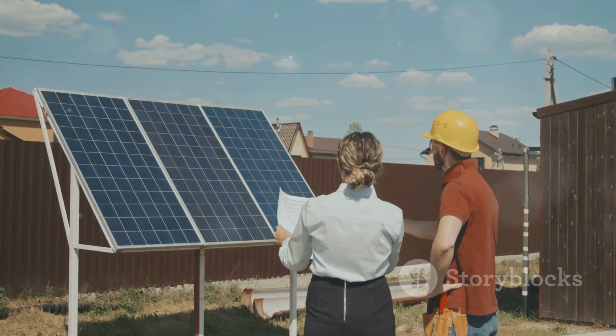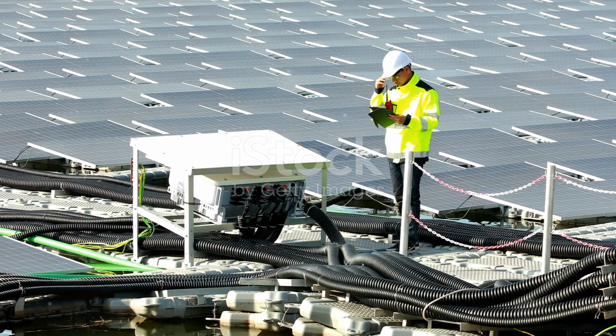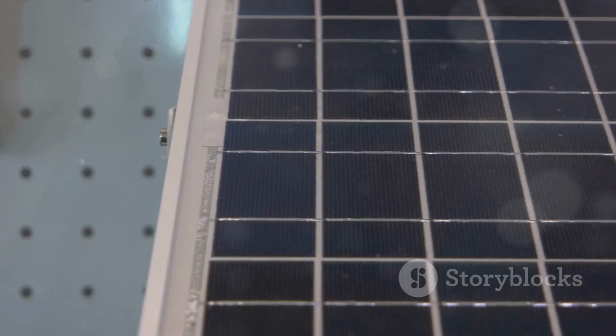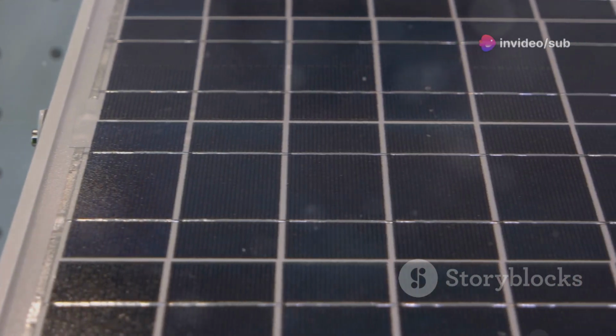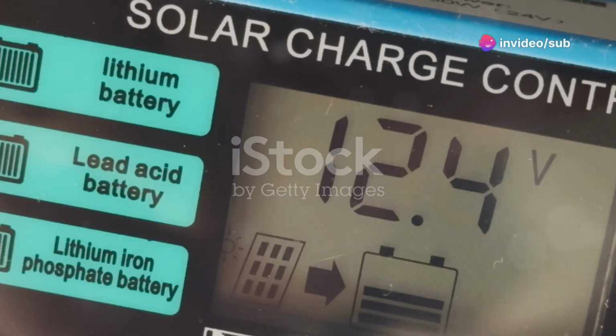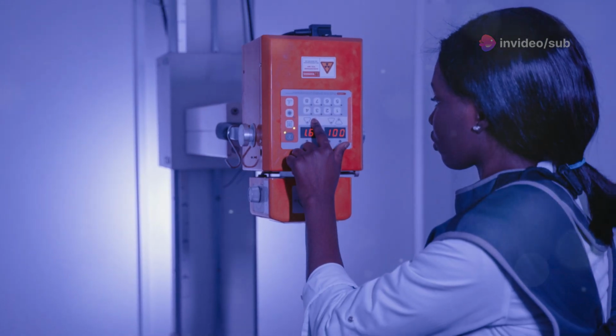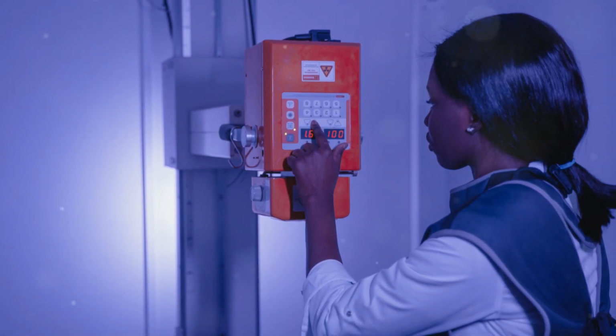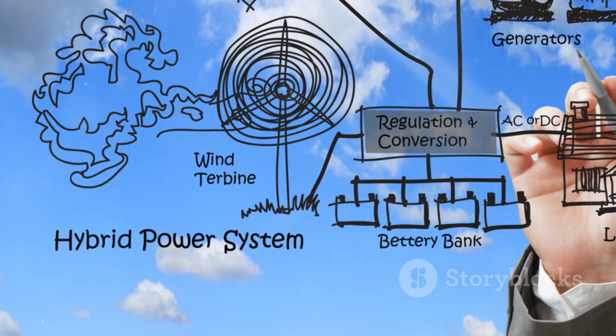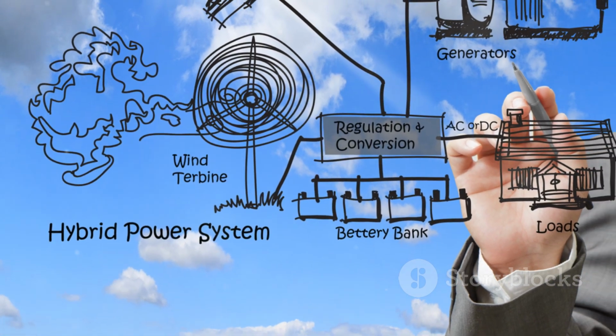Now it's time to test the whole system. Turn on the inverter and check if your solar panels are making power. The display should show how much energy you're getting from the sun. Check the battery monitor as well, and make sure the batteries are charging when the sun is out. If the grid goes out, use the ATS test button or just turn off the main breaker. Your essential loads should keep working from battery power.